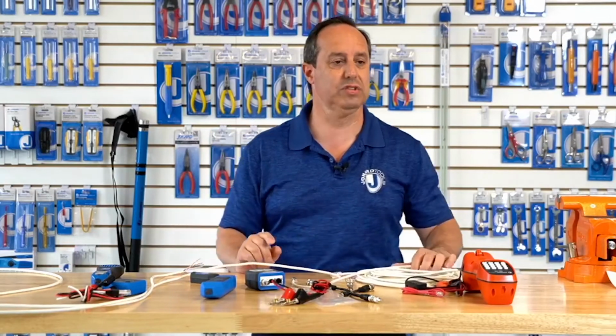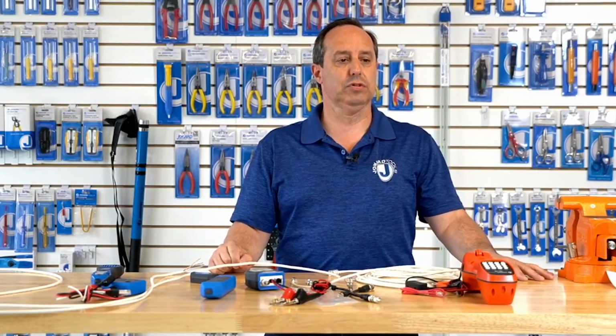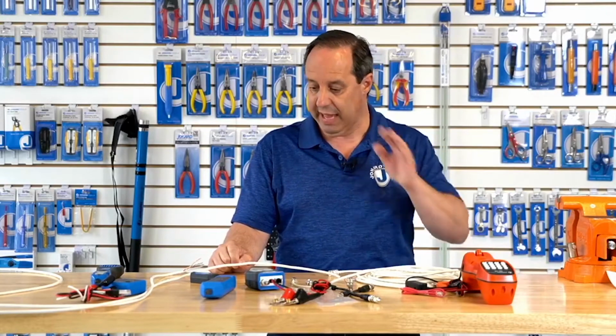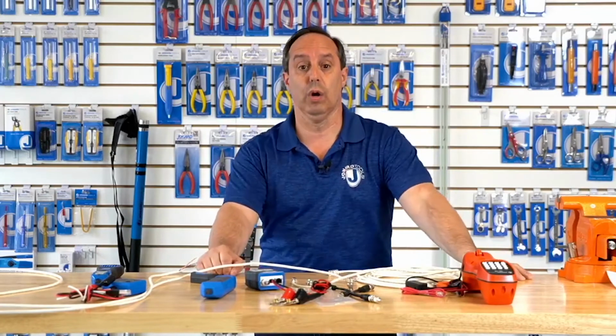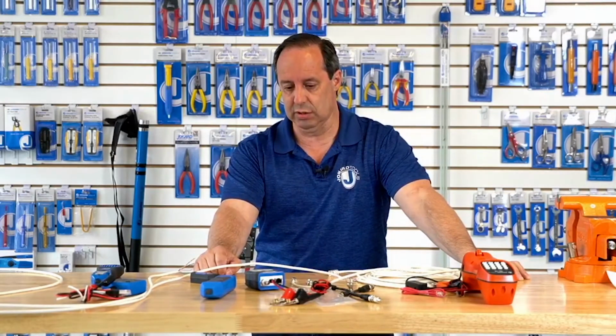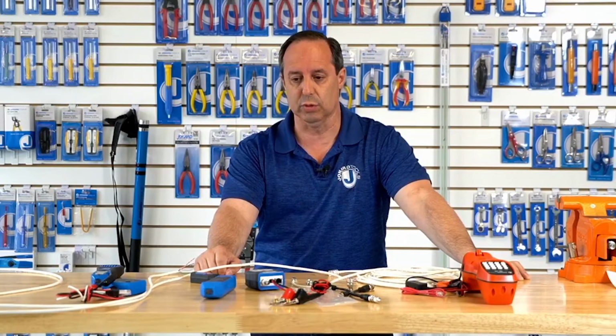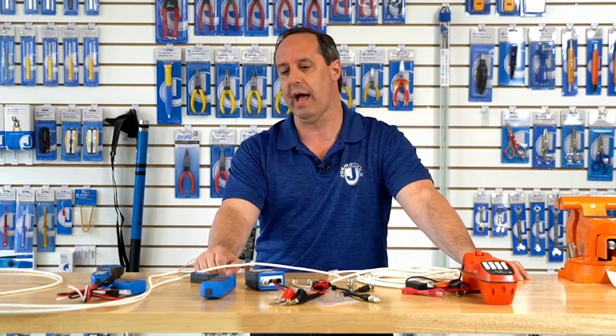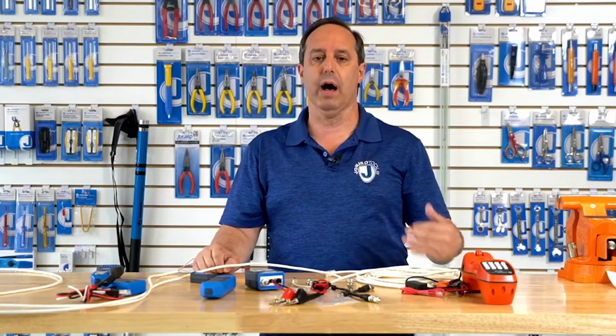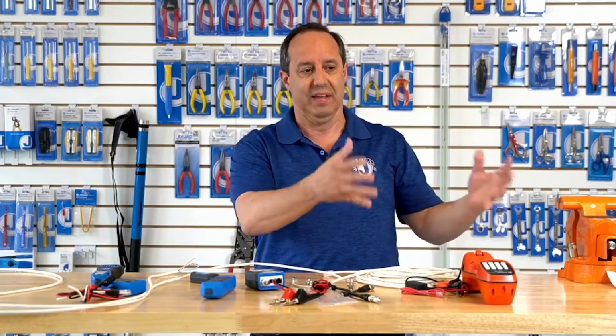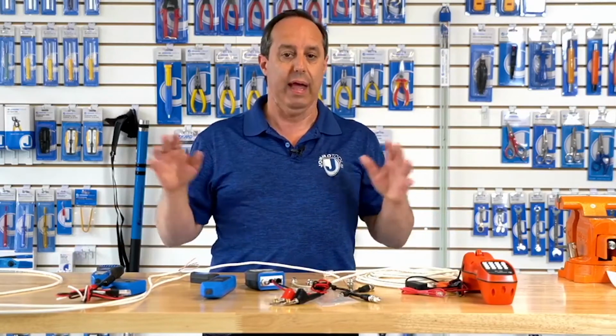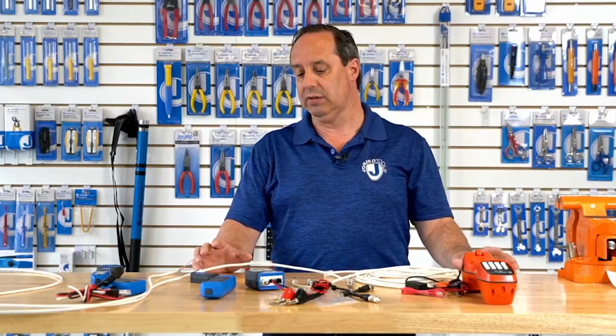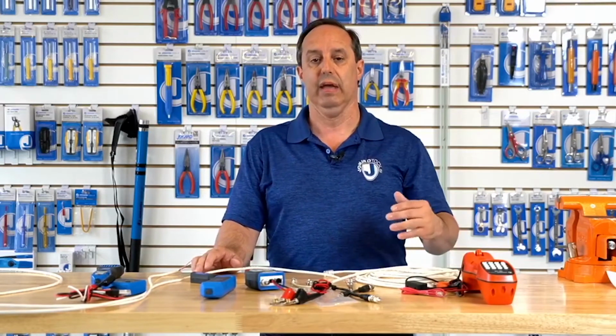Another question: can you use your tone and probe on live circuits? Really, the answer is no. You don't want to hook it up to a live circuit. Ideally, when tracing, you want to stay away from any live circuit, because the probe will pick up electromagnetic interference from it, which comes across as a loud hum depending on strength, and it can overpower the tone in your cable so you can't hear it. To avoid that, you'd need a digital or filtered probe.